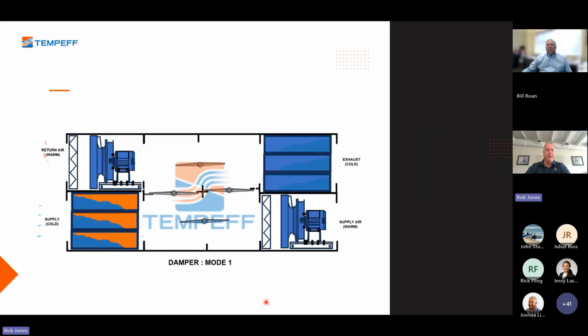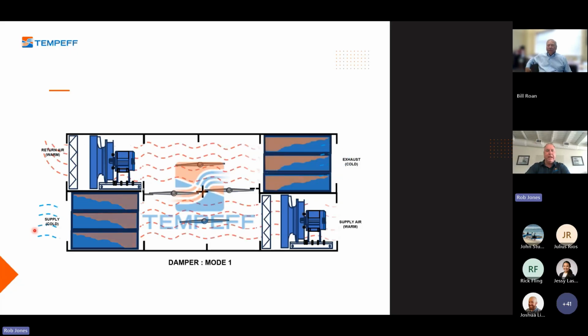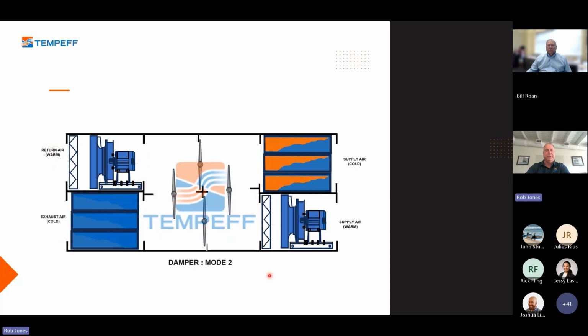This is it in action. So what we see here is the return air coming back. It's being directed over to energy core A, and energy core A is gradually warming up over that 60-second cycle. Down on the other side, we have the outdoor air coming through the pre-charged energy core B, being warmed and into the supply air. And of course, once the cores are expended, the dampers will shift, and now it does the U-turn configuration.